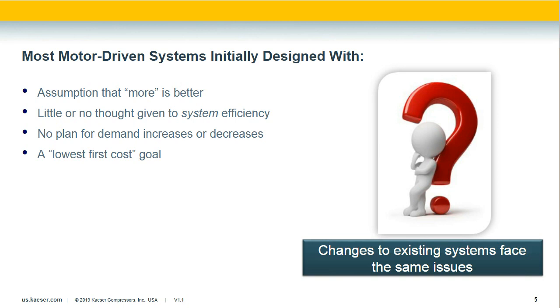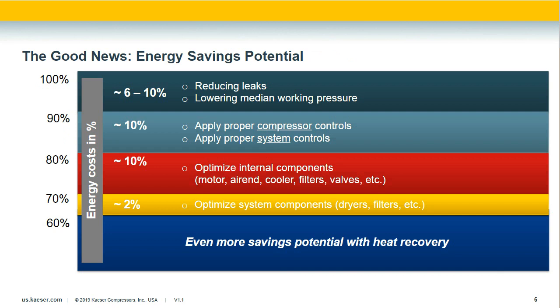If prevalent attitudes can be overcome, there are very effective ways to make improvements. Fixing leaks alone can generate energy improvements of 6% to 10% — a very conservative number. Choosing proper compressor controls and managing multiple compressors from one device can offer significant energy savings and improved pressure stability. Reducing pressure drop with good maintenance practices and air treatment selection also pays back. And if you can tap into your compressor as a heat source, you can get even further ahead.